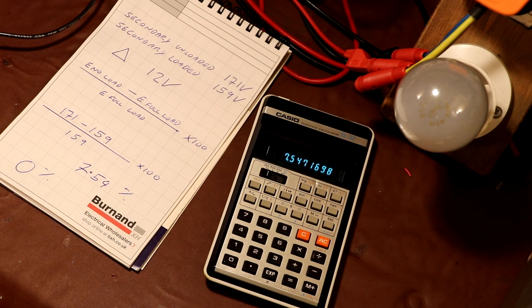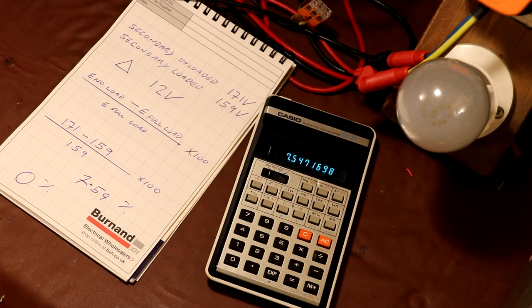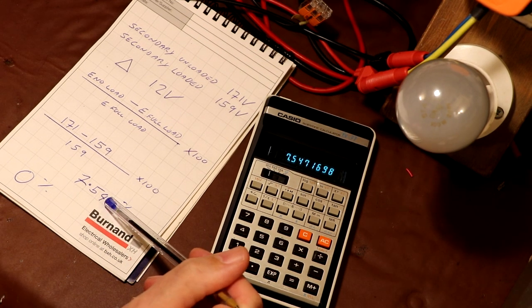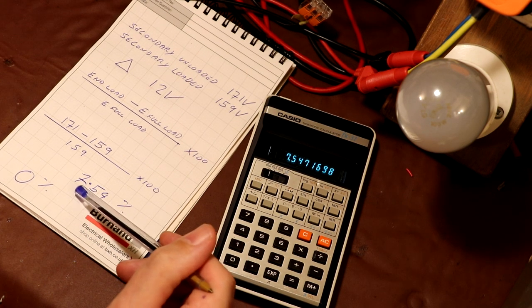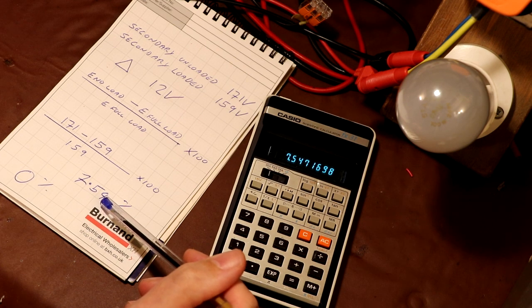Now for a modern low voltage transformer, regulation figures are typically between 4 and 6%, but for very high voltage transformers above perhaps 33 kilovolts, that figure can increase quite a lot, where it might be as high as 13%. So given the age of our transformer and given how crudely it's constructed, I don't think our figure of 7.5% is too bad.